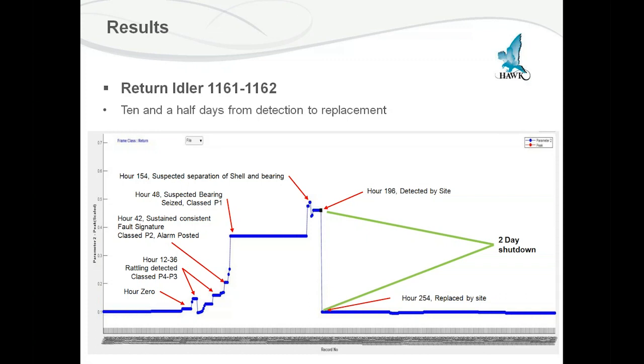If you listened to a recording of a good and bad roller side by side from our system, I have questions on whether a human being is able to reliably pull one from the other. One of our factors is actually the change in signal over time. Bearings that are failing change over a time period. As you can see, they're not static. And even in here, there is some averaging going on to get these nice flat graphs for display. There is some day-to-day monitoring, and it's that movement of the actual parameters that changes. I don't know whether that'd be doable, but we have no problem giving you that information. It's a lot of data though. You're talking about multiple gigs a minute, depending on the length and the speed that we're running the unit at.